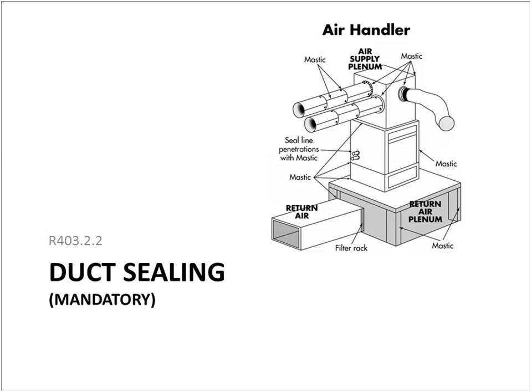However, air sealing is required, and that's required in every circumstance with ducts. It has been required for some time, but it hadn't been spelled out. It's been mandatory under the mechanical code, but not under the Michigan Residential Code. So now it is in the Michigan Residential Code. So all ducts need to be sealed. And this slide shows you the areas where mastic or an approved sealant tape can be applied.